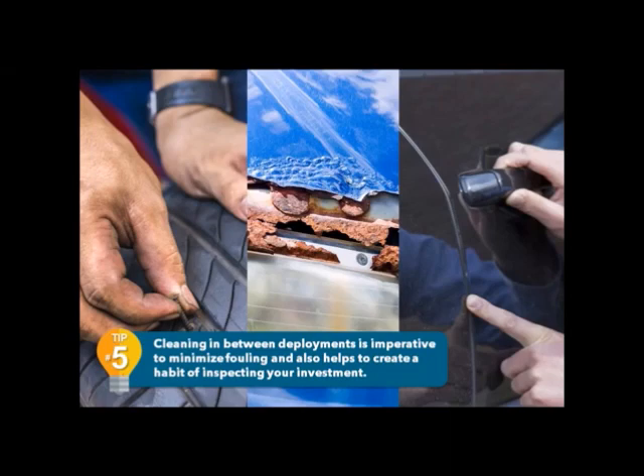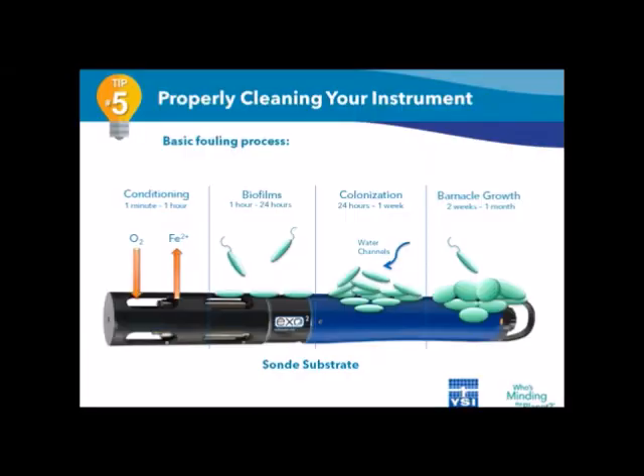Cleaning in between deployments is imperative to minimize fouling, and it also helps you create a habit of inspecting your investment. Regular cleaning helps to minimize biofouling too, because it removes the biofilms that microorganisms create. When microorganisms adhere to your instrument surface, they become problematic in a few ways. They condition the instrument surface, which provides an enzymatic interaction exchange for nutrients. Then they provide protection against environmental stressors, and this also increases resistance to biocides. Once formed, they change the surface chemistry of the instrument, which can lead to macroorganism growth like barnacles. They also interrupt ion flow, acting like a diffusion barrier, which can lead to localized corrosion.